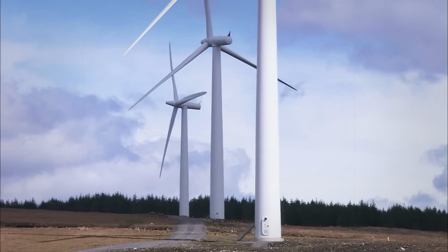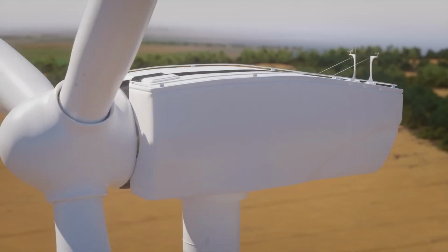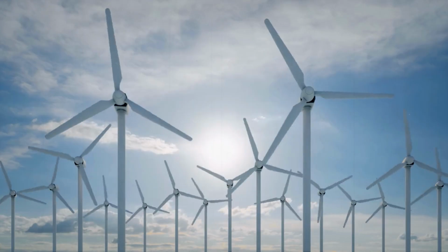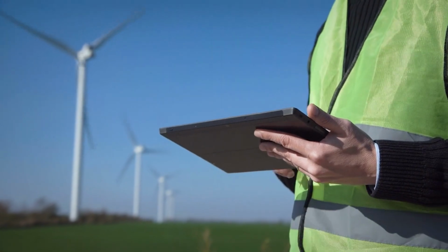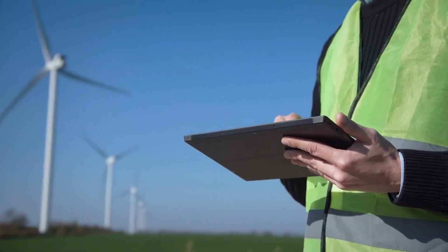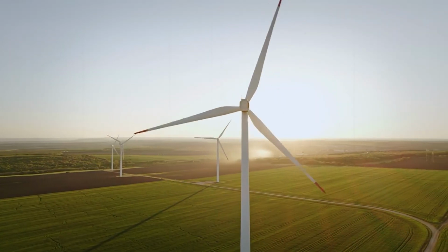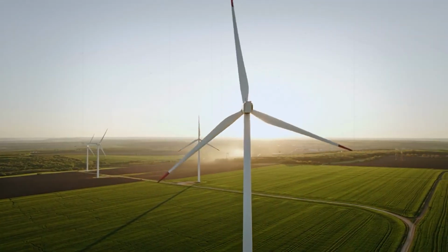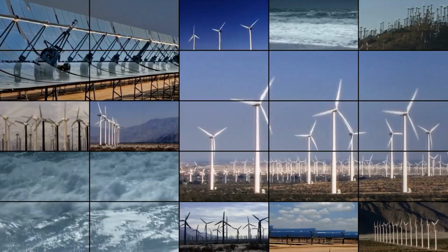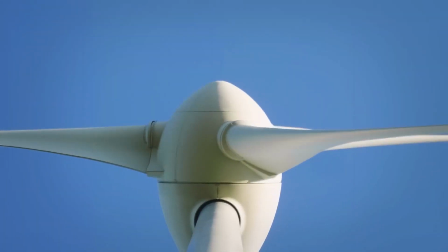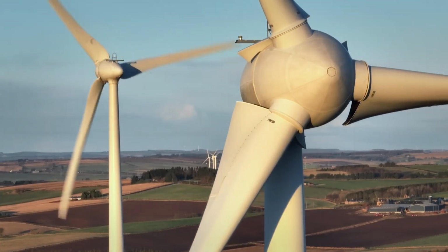Erosion lowers aerodynamic performance. If erosion is not repaired, it may cause a loss in energy production of up to 5% per year. Severe erosion makes future repairs more costly, and it may even require complete replacement of the leading edge. You can identify erosion by visually inspecting the leading edge and the blade tip for signs of pitting, thinning, or scratches. In order to get a comprehensive perspective of surface wear, you need to use drone scans. Compare the current erosion with the data from previous inspections to track its progression.